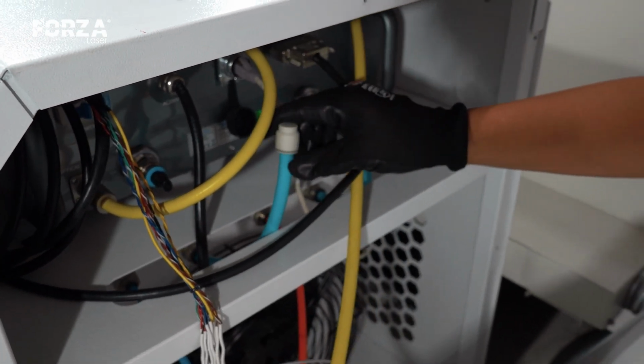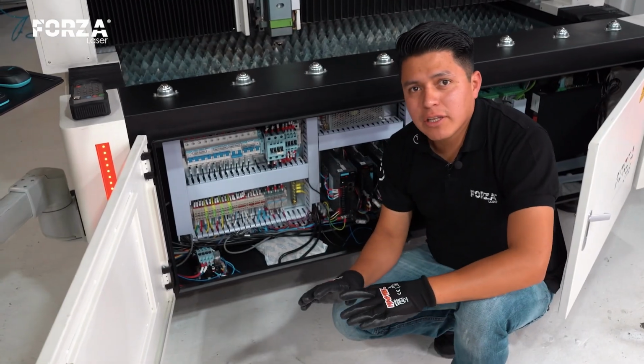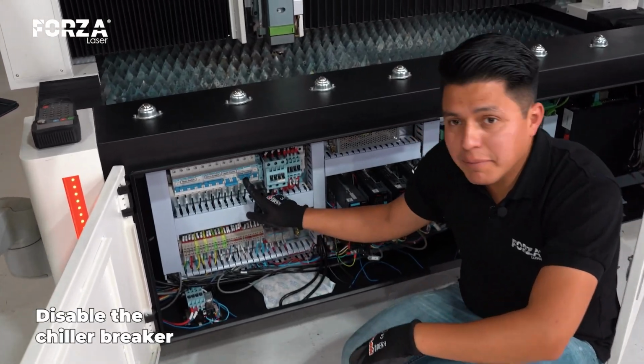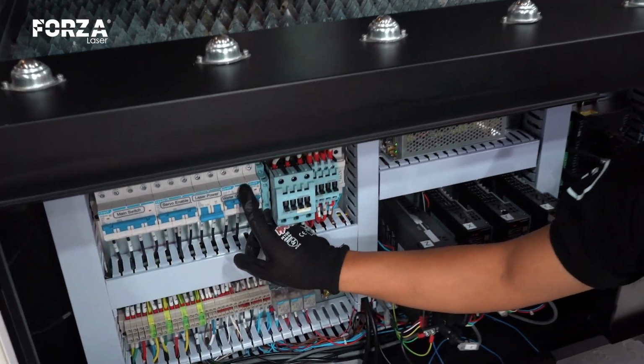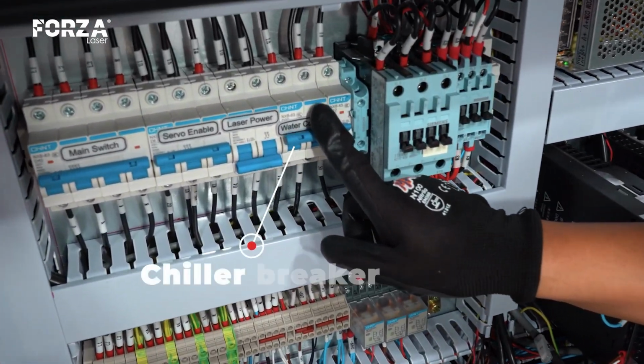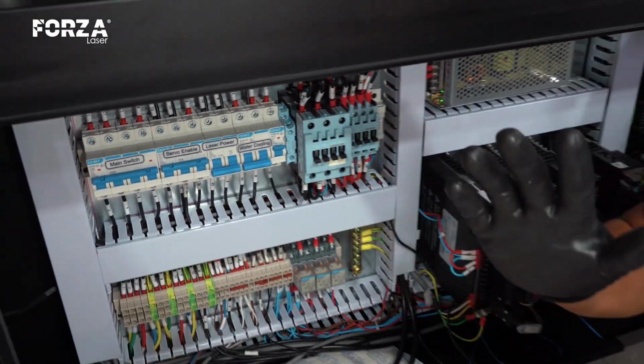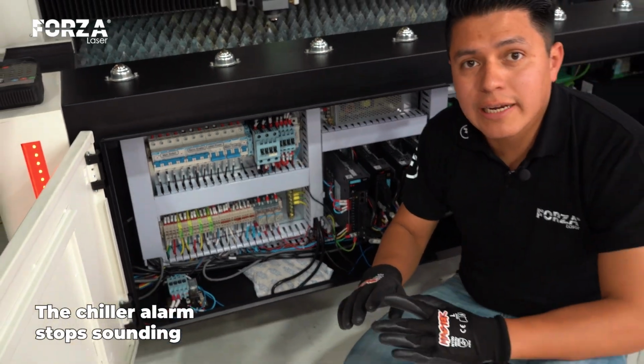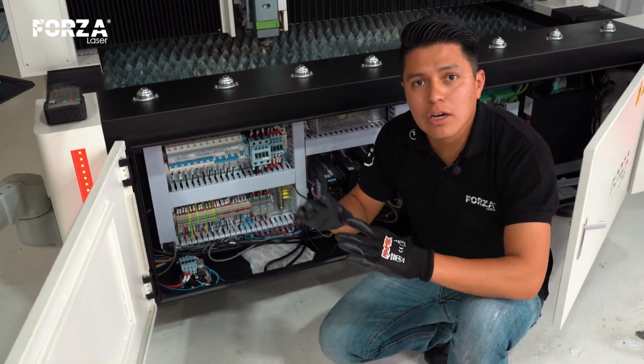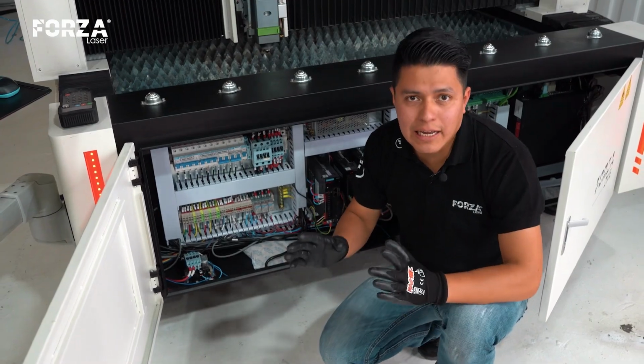We need to turn off the chiller first, before attempting to remove the cap. This is absolutely crucial because, as I've mentioned, the water flow is quite strong. We then proceed to disable the breaker to ensure the chiller powers down. I'm not sure if you could hear it before, but now it has completely stopped making any sound. At this very moment, we are going to perform the connection to resolve the alarm.